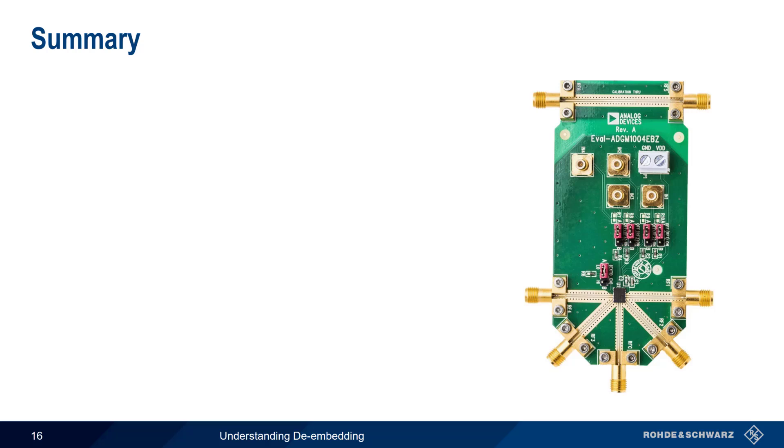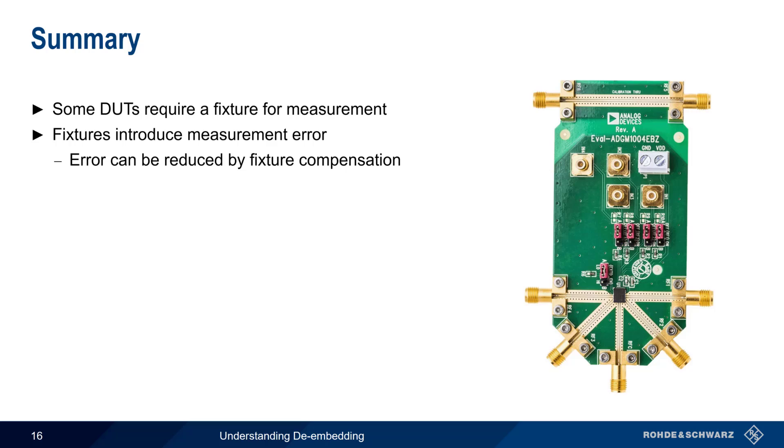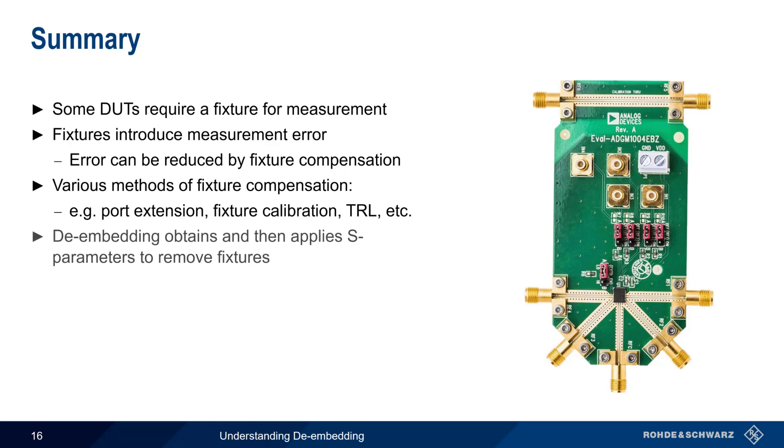So let's summarize what we've covered. A fixture is sometimes required in order to measure a DUT, for example, in the case of a non-connectorized DUT. This fixture, in turn, can introduce some level of measurement error, especially at higher frequencies. We can reduce the level of error by using various methods of fixture compensation in order to remove the effects of the fixture, and there are a number of different ways of doing this, such as port extension, fixture calibration, TRL, etc. De-embedding refers to a process whereby we use S-parameters to create mathematical models of a fixture's frequency-dependent behavior, and 2x through de-embedding is one example of a modern de-embedding methodology that's become popular due to its speed, accuracy, and simplicity.